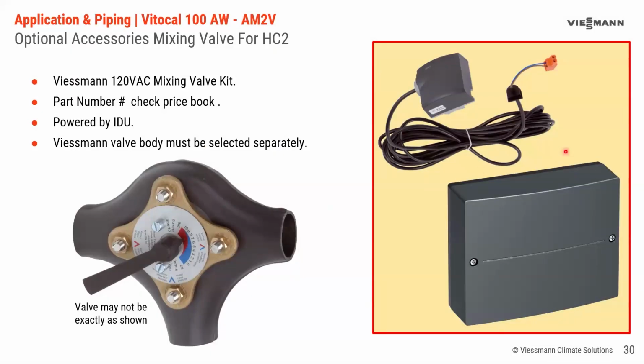You're going to buy two parts. You're going to buy the mixing valve kit, which is the motor actuator and the strap-on temperature sensor. This is a 10K NTC thermistor, and that's what the heat pump is going to be looking for. And the valve body. This valve body shows a welded valve, and that's not necessarily a welded valve. That's why it says may not be exactly as shown. And this would be ordered as a separate part number.